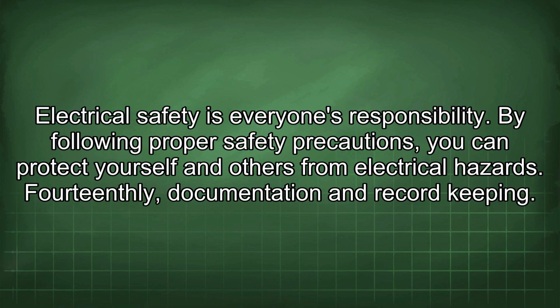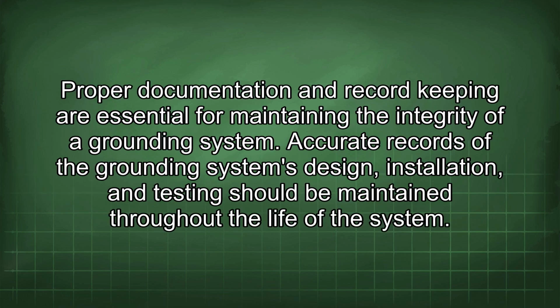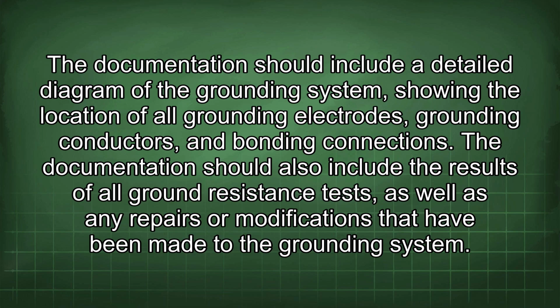14th, documentation and record keeping. Proper documentation and record keeping are essential for maintaining the integrity of a grounding system. Accurate records of the grounding system's design, installation, and testing should be maintained throughout the life of the system. The documentation should include a detailed diagram of the grounding system showing the location of all grounding electrodes, grounding conductors, and bonding connections. The documentation should also include the results of all ground resistance tests, as well as any repairs or modifications that have been made to the grounding system.